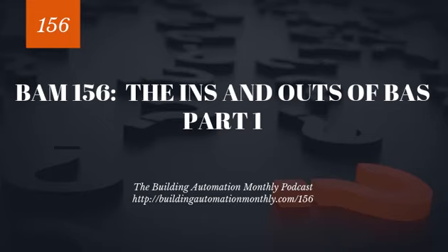So we have analog, binary, multi-state. Analog are variable. Binary are two states: on, off, true, false, normal, alarm. Multi-state is, guess what? Multiple states. For example, occupancy: occupied, unoccupied, standby, etc. So pretty straightforward, right? Now you carry that entire concept of analog, binary, multi-state across values and outputs, and they are consistent. You're going to have two states with binary values.